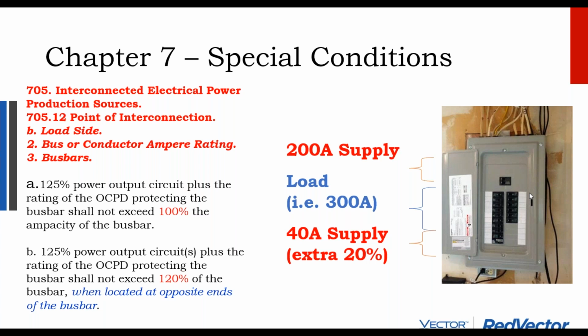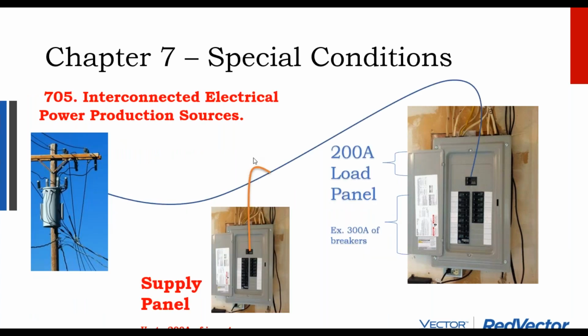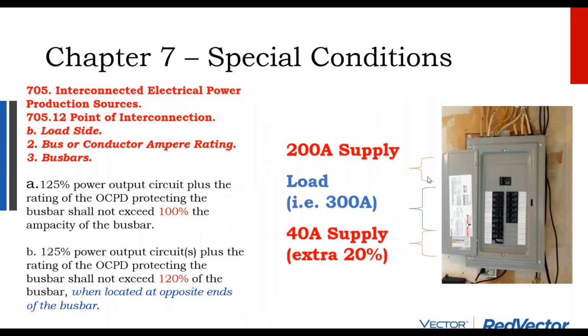And so if this were not a load panel, if this were a power distribution panel for solar only, like on a utility scale project where you're combining a bunch of solar arrays together, you would have 200 amps of solar on a 200 amp panel. If you're doing a supply side connection and this is a 200 amp panel, you can have 200 amps of solar plugged in to these 200 amp conductors, and the power either comes from the grid or it comes from the solar array. But under no circumstance does 200 amps of supply go through the panel, because you're protected by this main breaker.